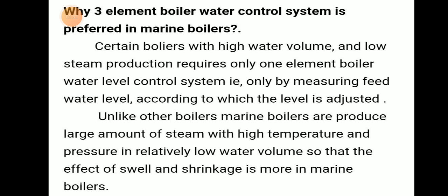But unlike those boilers, marine boilers produce a large amount of steam at high temperature and pressure with relatively low water volume. So the effect of swell and shrinkage is more in marine boilers. So here comes the use of 3 element boiler water level control. You can understand, right?